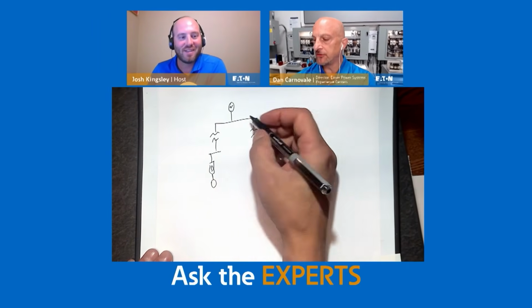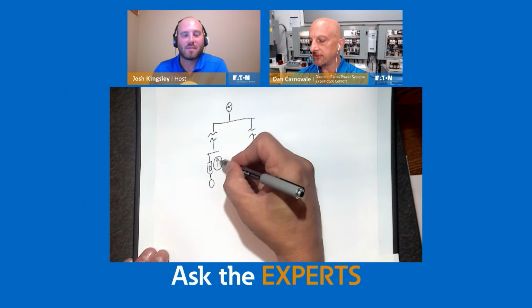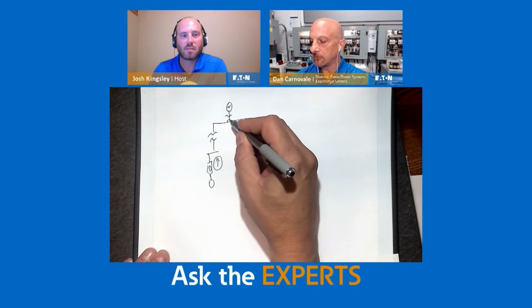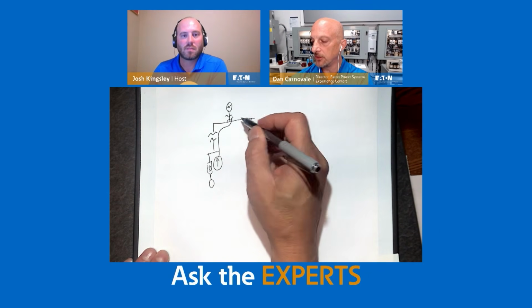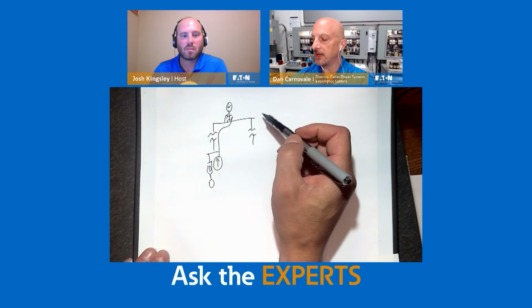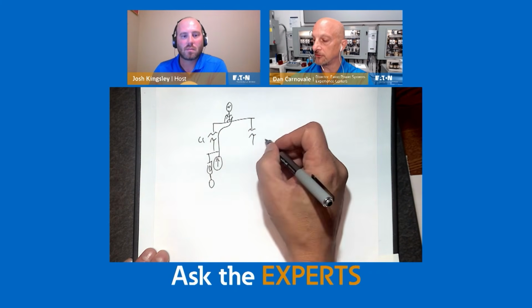So if you have, again, a single utility source and let's say multiple customers or multiple transformers that are fed off the same source, sometimes you end up with basically what would be the harmonics coming from one customer affecting, let's say in a VFD scenario, something like that, affecting another. Real quick, can we pull up his drawing on the screen as well? Yeah, sorry. Go on. Yes. So as these harmonics come out of this system here, again, there's always transformers back through the system. So if this current is affecting this transformer, it might actually cause damage to that, and this customer could see it. So this is customer 1 and customer 2.